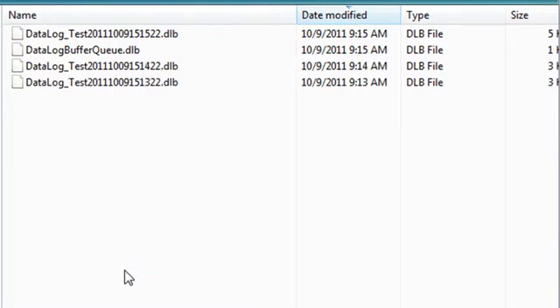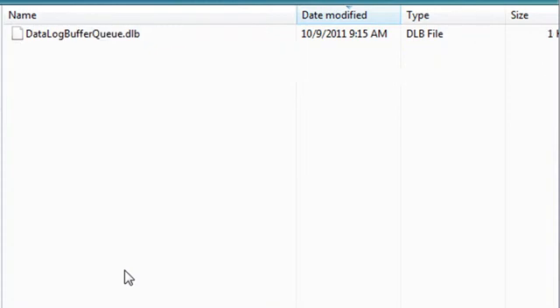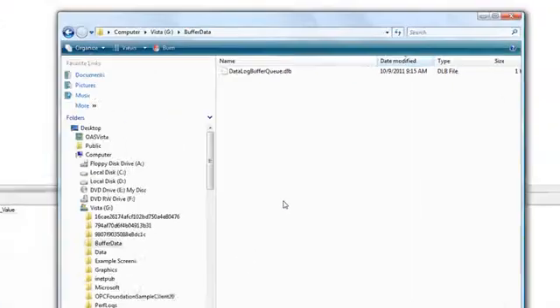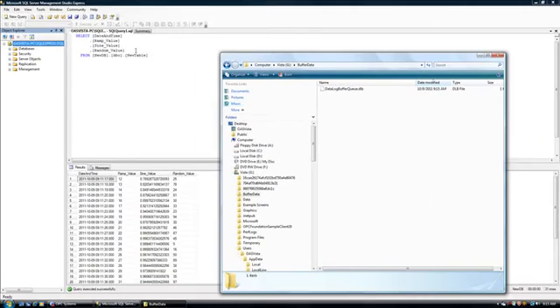These buffer files are processed one at a time at a 100 millisecond execution rate. So to the human eye, they move out pretty quickly. But if you're buffering data for, say, several months, you don't want to overwhelm your network or your database engine when the connection is restored. So it moves the values out of the buffer files in chunks at a time. There the buffer files have now disappeared.